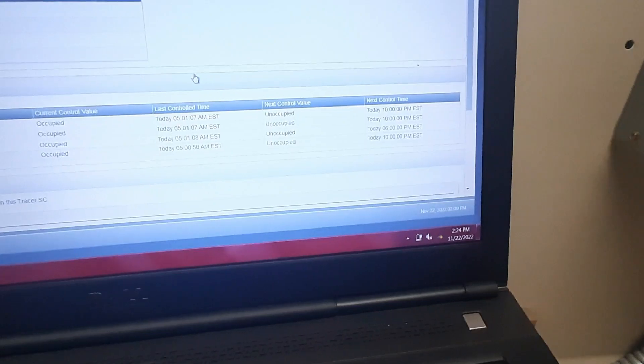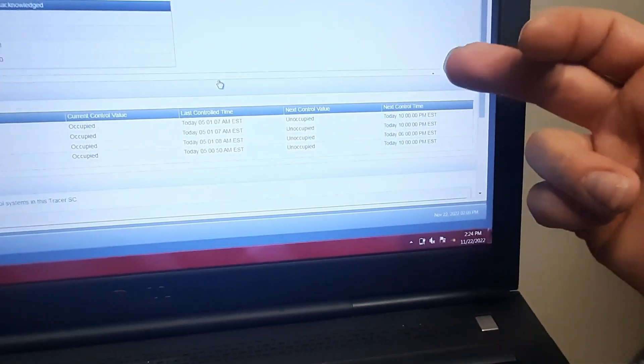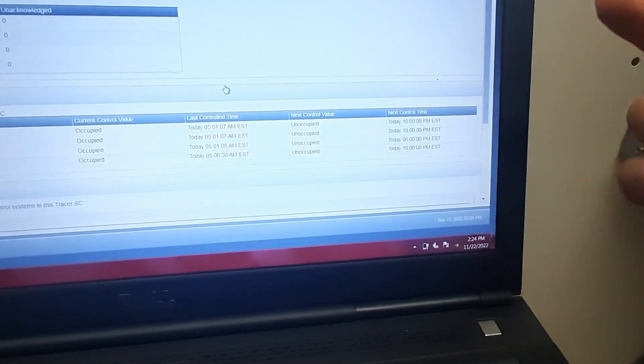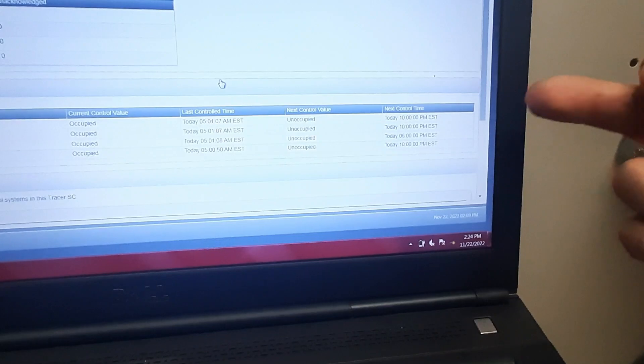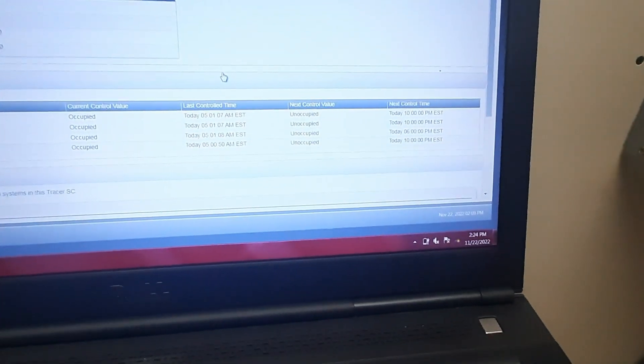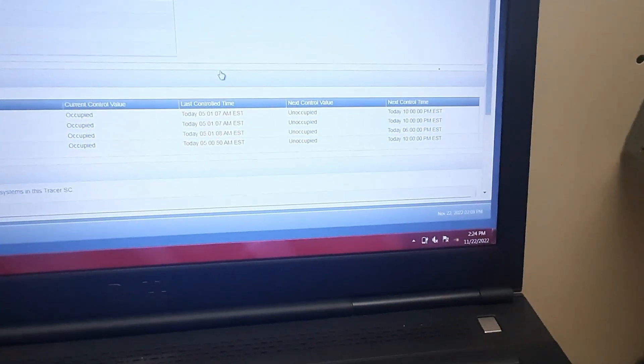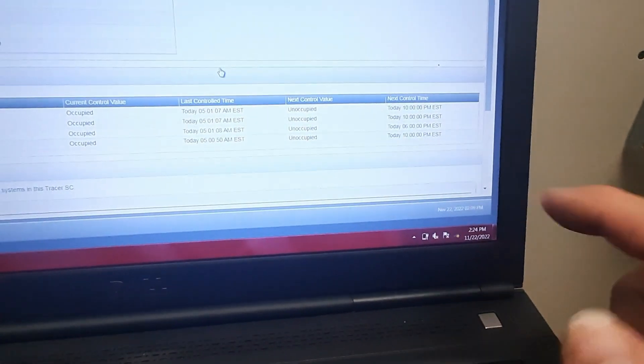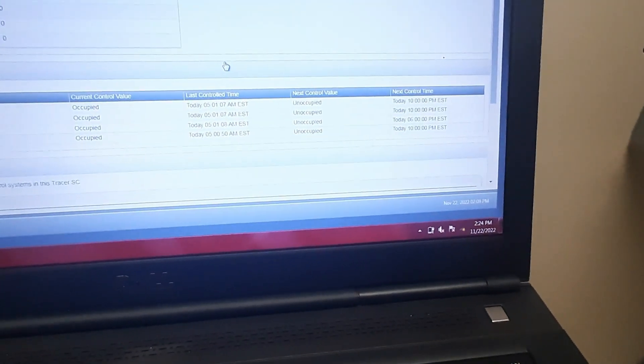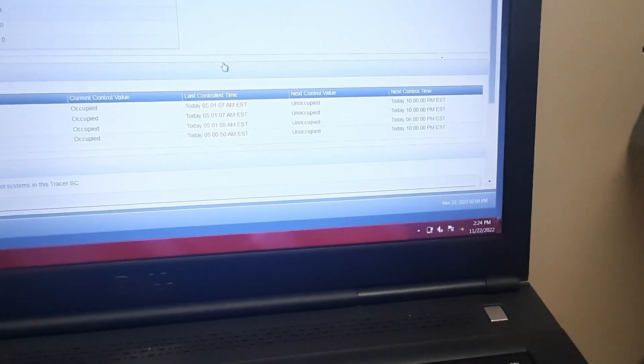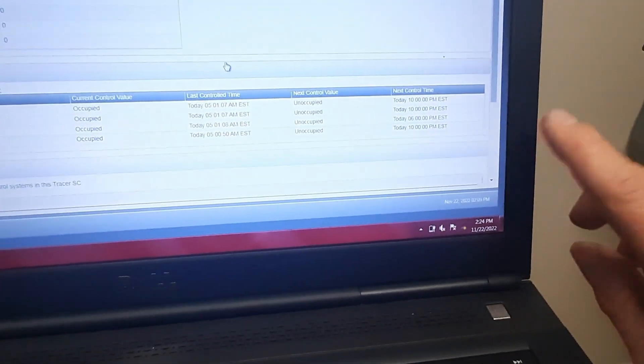So let's get logged in and see what we can figure out. We can see here about 5 a.m. they go into occupied, next control time 10 p.m. They go in unoccupied, except the one space goes in at 6 and yeah that's a meeting space so it shouldn't matter there.